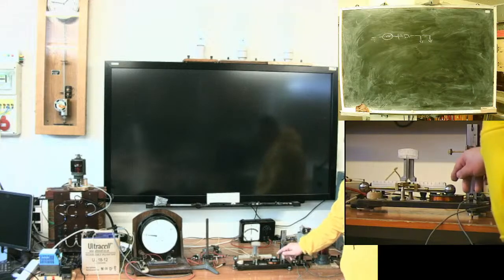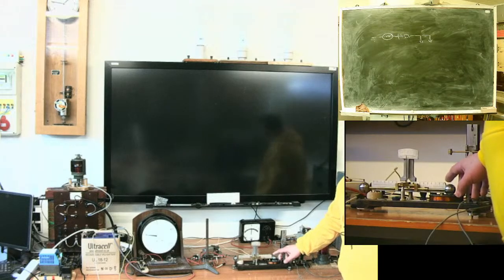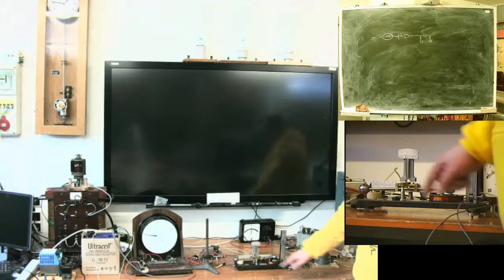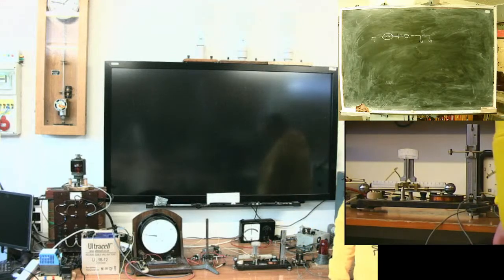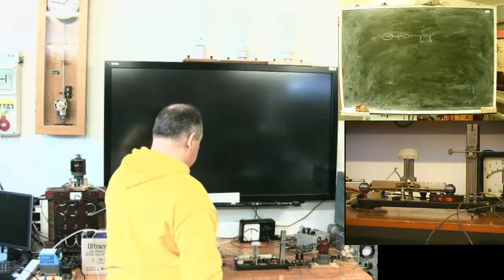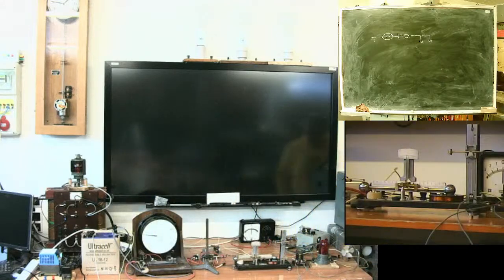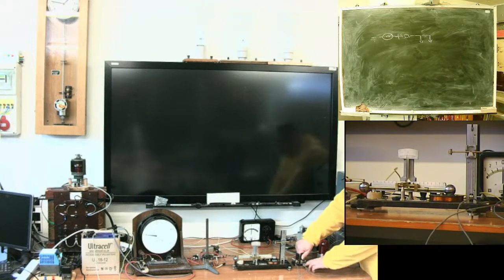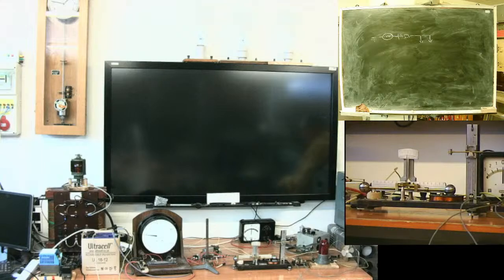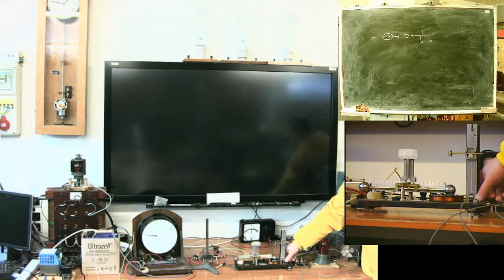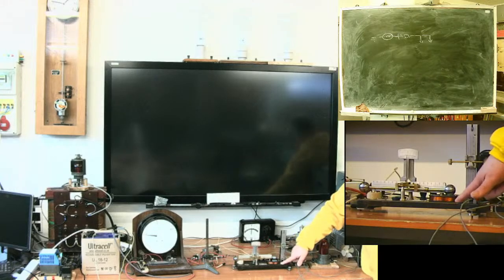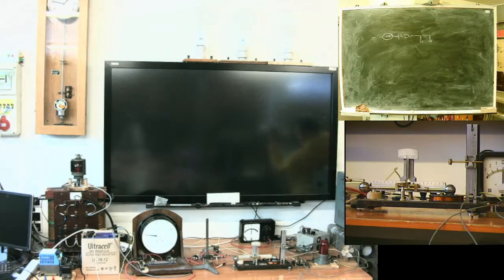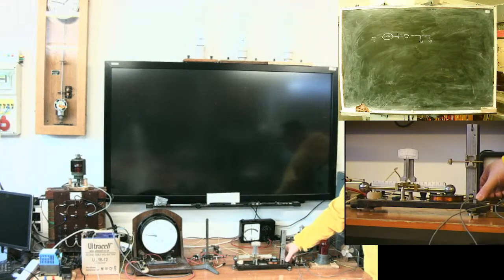If it tilts like this, can you hear? Yes. It's a trip signal. Here is the network current, and this pair is my load. Also, I have a magnet on a movable arm here. If current flows in the coil, it pulls the ball down. The magnet pulls the ball up, like this.